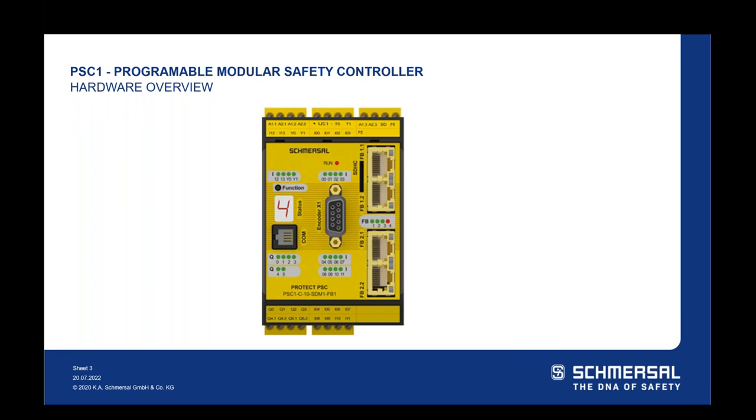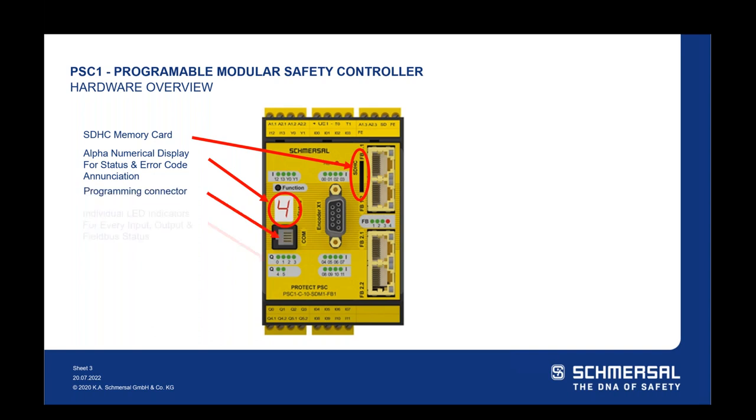I'm going to jump into the first slide — a hardware overview. On the PSC-1 safety controller, there are a few hardware features I want to highlight. The first is the SDHC memory card slot, which is external memory you can use for loading new programs or retrieving programs from a safety controller in the field. There is internal memory, so the memory card is not required. There's also an alphanumerical display for status and error code annunciation for the PSC-1 C-10, so by opening a control panel you can see fault or alarm codes and whether you are in run mode.